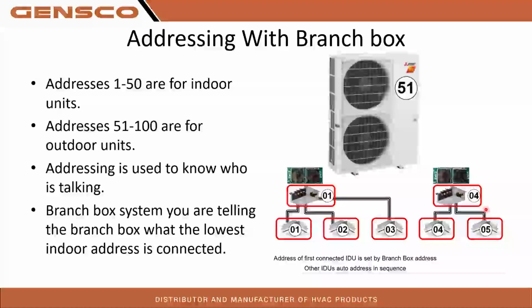One thing you can do is say you have a 5-port branch box here, and you only got 3 heads on there for this example, because you're planning to do future expansion. You know this customer is eventually going to add a couple more pieces of equipment to this thing, but you don't want to have to readdress the system when you do. No problem. If this is a 5-port branch box and we're only using 3 of them, just skip those 2 addresses on the next one.